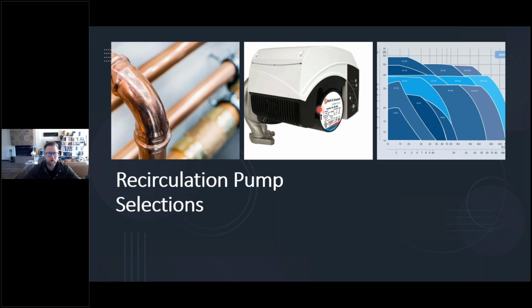However, the use of variable speed, these ECM type motors for recirculating pumps, was recommended, especially for healthcare facilities. And the reason for this is, rather than having to swap out a whole pump, you could select a point. Let's say this is our curve here. If you selected a point down here, you had a lot of wiggle room to increase head or increase flow as needed for your system. And that was the real beauty of these pumps. So we saw it as an opportunity to fine tune your system and give the owner more control. So that was one of the recommendations that came out from that document for consideration.